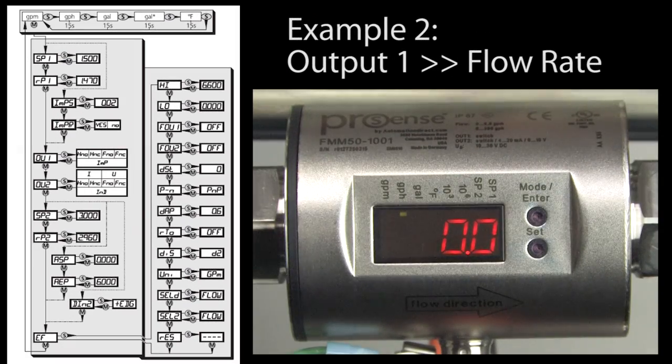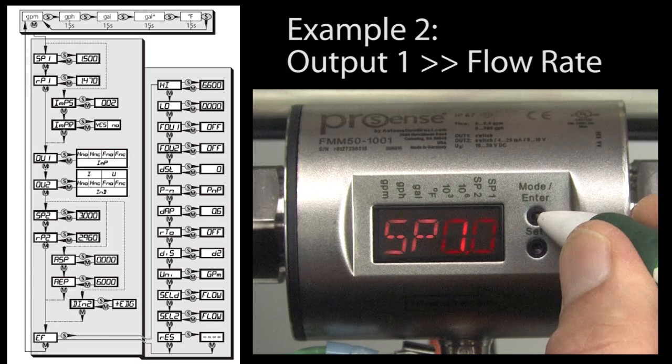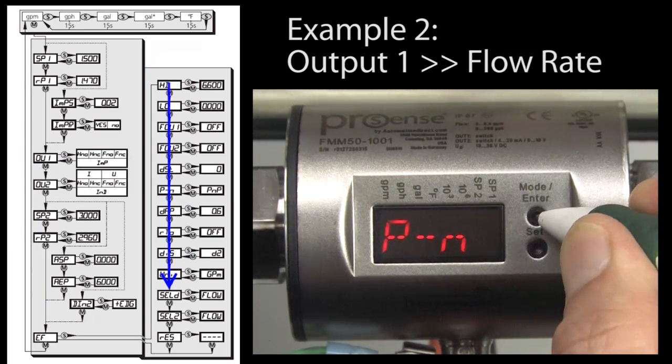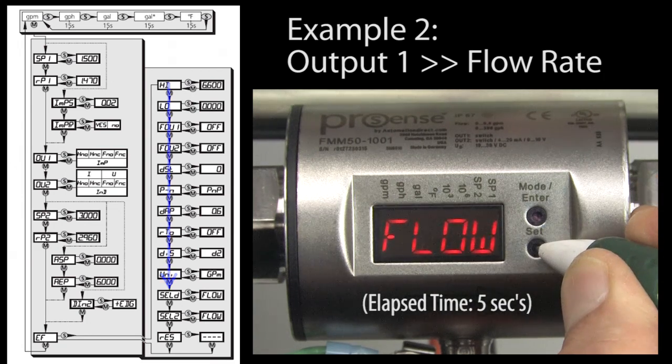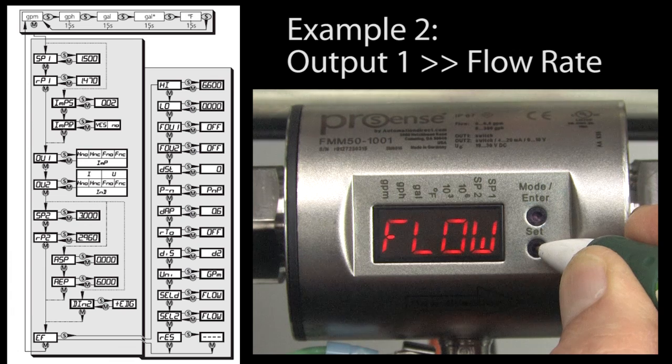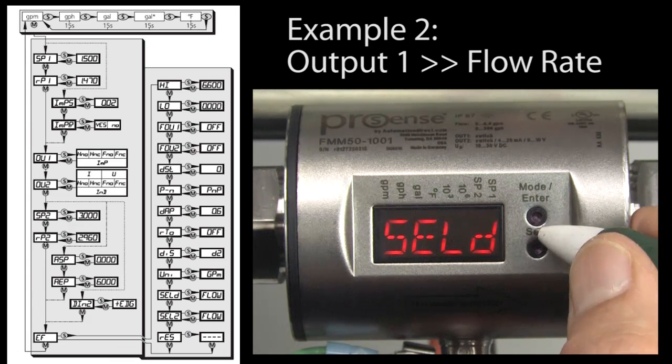Let's do another one. Let's set output 1 for flow rate monitoring. So we press the mode button to get to the extended functions menu and then SELD to select output 1's mode. Hold down select until it stops blinking and then cycle through the options until you get to flow and then press mode to accept.